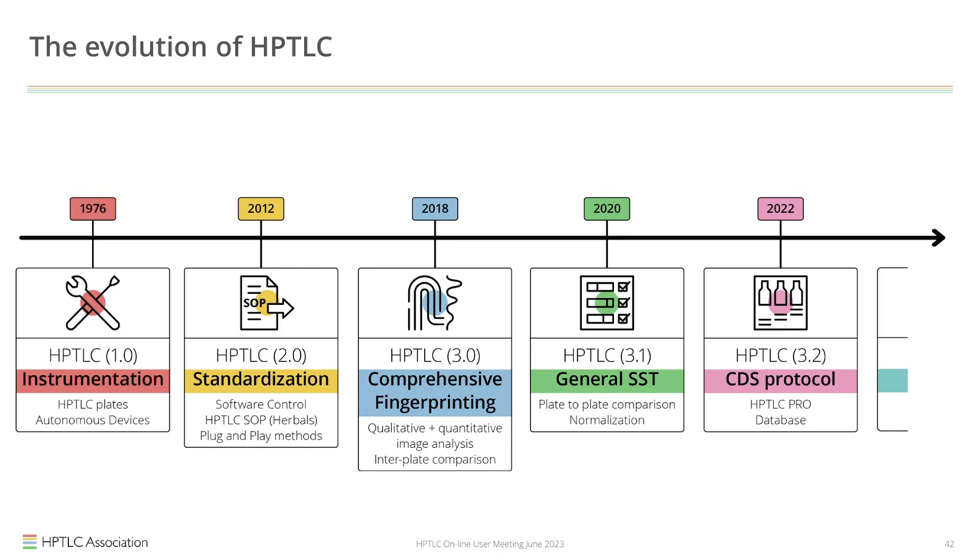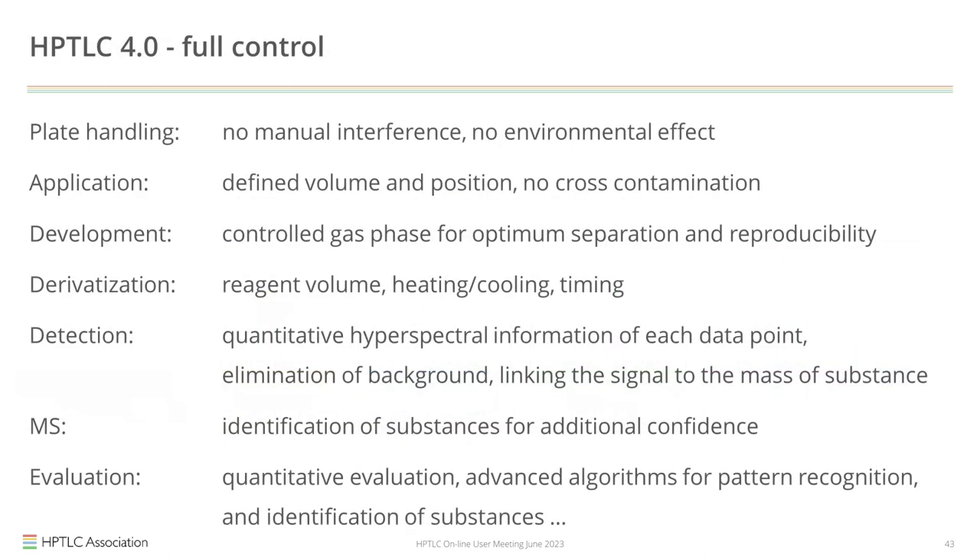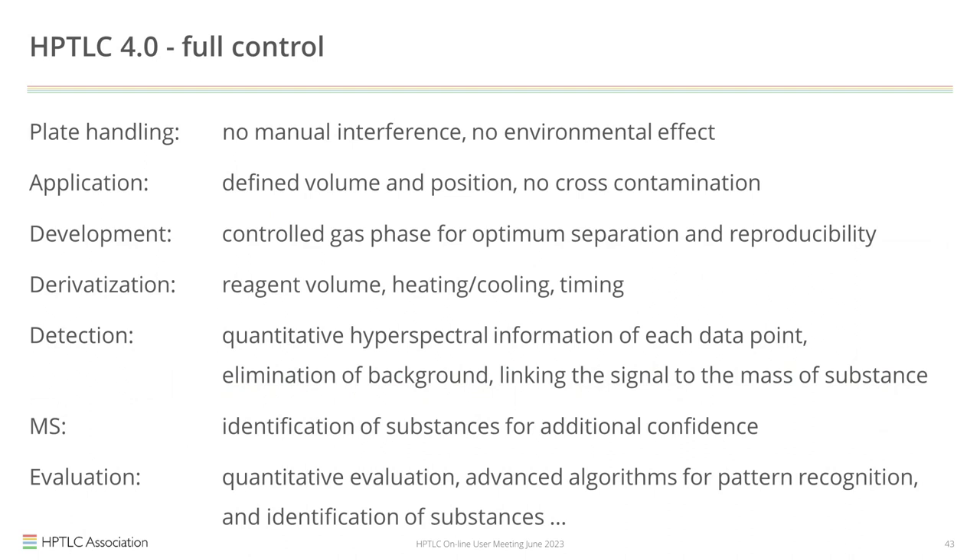Now everybody is waiting to hear what HPTLC 4.0 is. HPTLC 4.0 is full control of HPTLC for each step, starting from plate handling with no manual interference and no environmental effects. Application is done with a defined volume and defined position without cross-contamination. Development is controlled by the gas phase for optimum separation and reproducibility. For derivatization, the reagent volume, heating, cooling, and timing are all specified in the method. Detection is done with quantitative hyperspectral information for each data point, with elimination of background and linking of signal to mass of substance. Mass spectrometry is included for additional substance identification confidence, and evaluation is linked to advanced algorithms for pattern recognition.